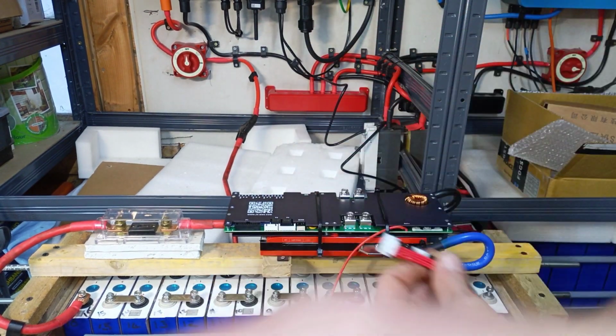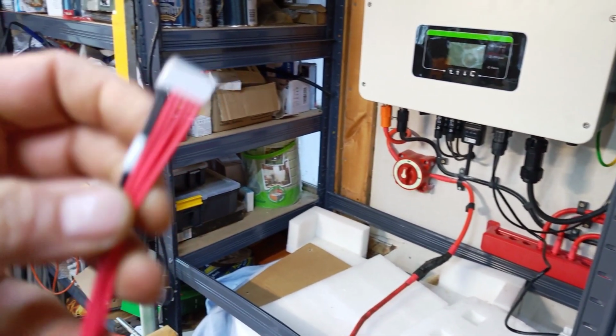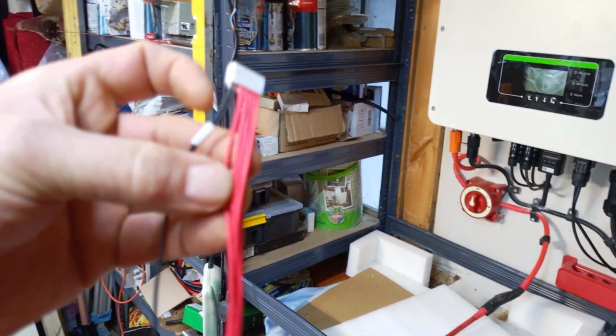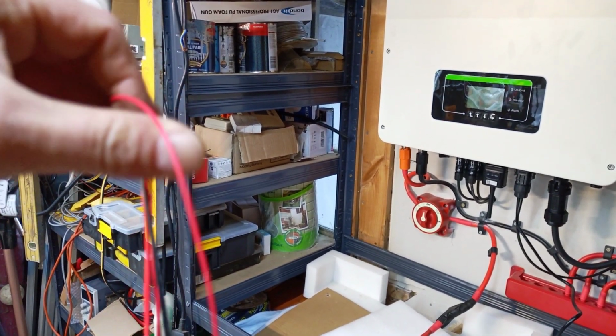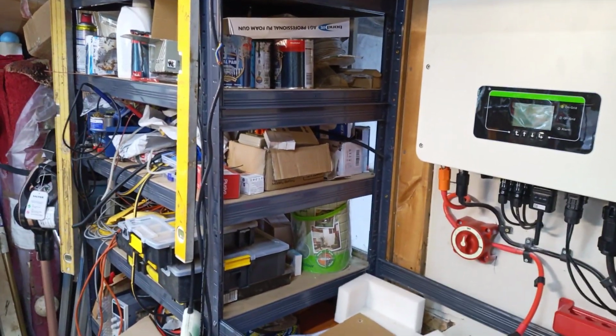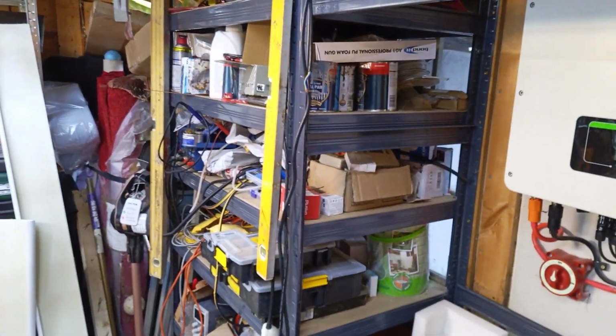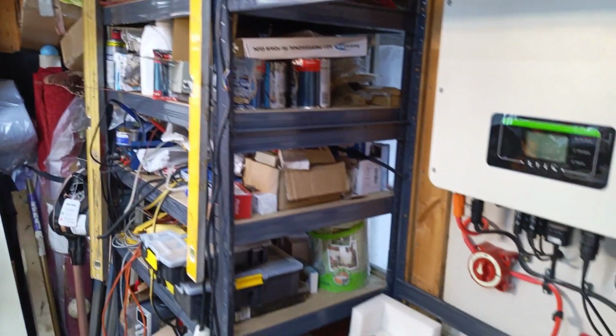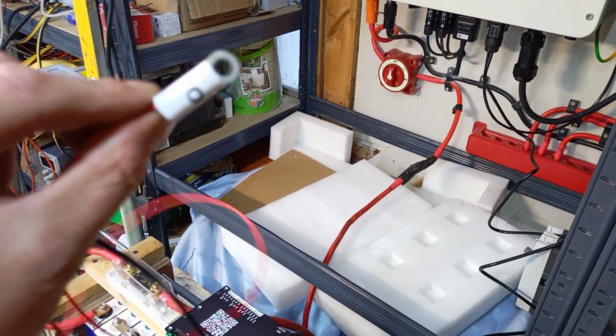The other thing as well is a wee moan with the new JK BMS: with the older version, it's a little more idiot proof, where you got B negative and then the most negative voltage sensing cable is black. Whereas in their infinite wisdom this time round, on the plugs for the balance leads, you've got temperature sensors there, and then they call that B0, which is the battery main negative, and it's red. So you've got to make sure you keep yourself sort of identified, otherwise you'll lose the plot. I know I'll lose the plot.